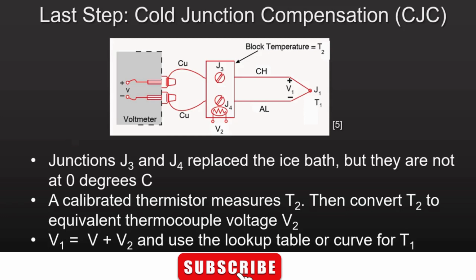We could use either a thermistor or an RTD to do this. We prefer a thermistor because it can be packaged into a small space, and our isothermal block will always have a temperature within the thermistor range.